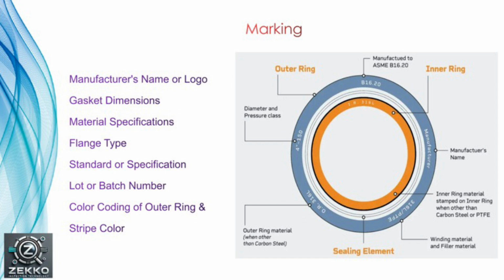In the slide, I have shown the gasket along with the identification. Here on the right side, the manufacturer's name or logo should be there on the ring. Then the inner ring is specified, the outer ring is specified. On the outer ring, that the spiral wound gasket is manufactured as per ASME B16.20 is the reference specification marked. Then dimension and pressure class are mentioned on the left side of the gasket. The sealing element is also marked on the gasket for identification.